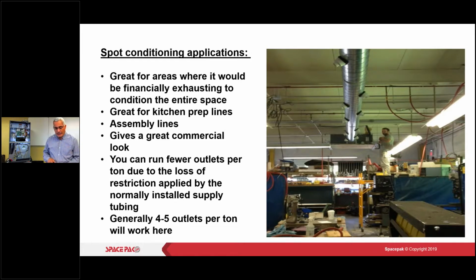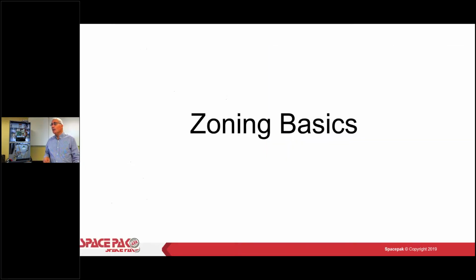And just to let you know, on occasion, I've had people ask, can I come off of the plenum with my 2-inch, but use a standard diffuser that we use in our conventional systems? And the answer is yes, you can, but you have to have a box built where it's at least, I believe, 4 inches deep. So when the air comes in, it has a chance to expand and go through that diffuser and not create any noise. So if that's something you're entertaining, give me a call, let us know, and we'll double check on what you're planning on doing. But I do believe about 4 inches deep, you'd have to make that box so you can spread that air out.